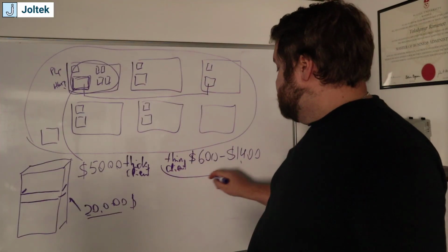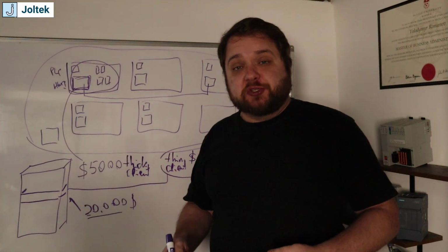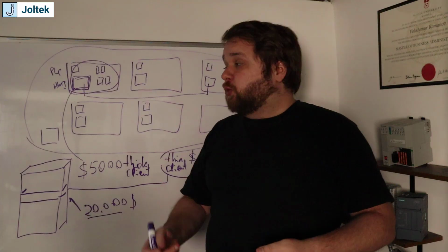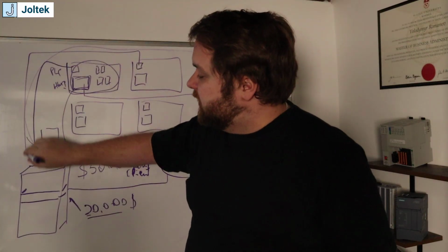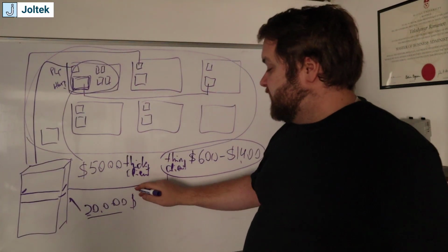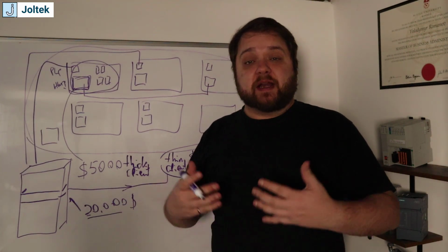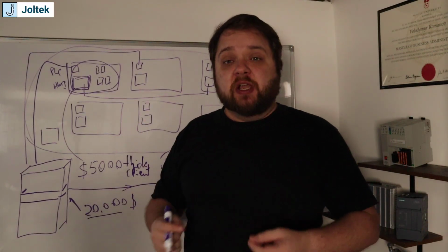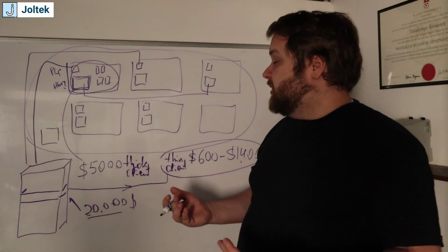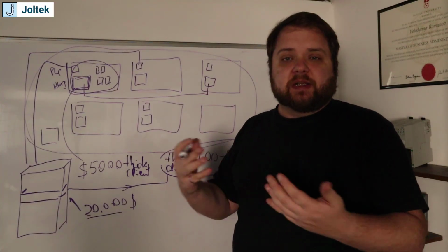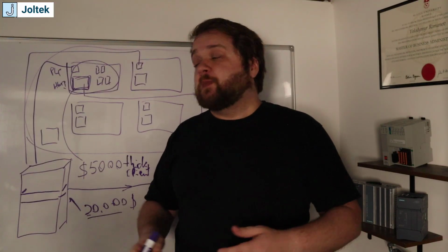capabilities. But what it's going to do is this thin client is going to maintain a near permanent connection to the server that is running this SCADA system, which is getting all the information from your PLCs into the server, again, into the application, and then servicing this information back to the thin clients. And so these thin clients are basically, again, HMIs, so they're going to be touch terminals, but they will only run a very small application. They do not require the entire capability of a computer. All they do is, like I said, run the application. Usually they're going to be Linux based because they're simply a lot leaner on that side.